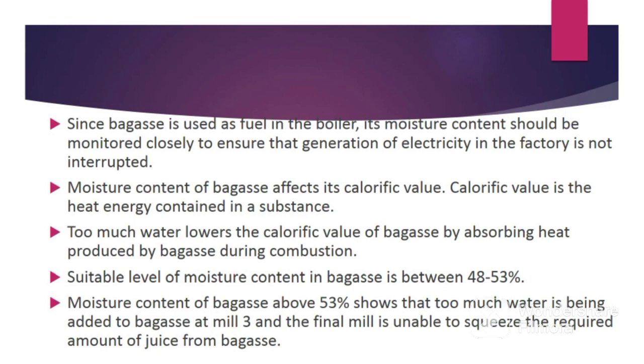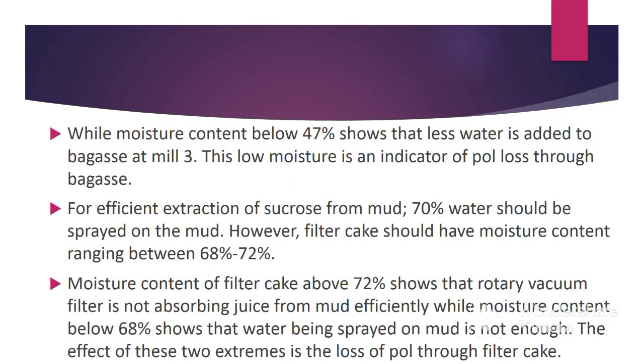Too much water lowers the calorific value of bagasse by absorbing heat produced during combustion. The suitable level of moisture content in bagasse is between 48 to 53 percent. Moisture content above 53 percent shows that too much water is being added to bagasse at mill 3, and the final mill is unable to squeeze the required amount of juice from the bagasse. Moisture content below 47 percent shows that less water is being added to bagasse at mill 3, which is an indicator of sugar loss through bagasse. Water is added at mill 3 to absorb and remove sugar remaining in bagasse for efficient extraction of sucrose.